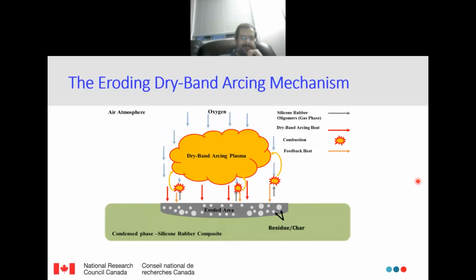Next, please. Now, this is another illustration to show how the environment, the surface, and the pollutant can all have a synergistic effect to damage the surface of the material. Here we have the silicone rubber material, and when you have dry bands, you start to have dry band arcing. So you have arcing in the presence of oxygen on the surface of the material. We have a plasma, because the arcing has a very high temperature, which can reach hundreds of degrees centigrade. This will cause some erosion, some char on the surface of the material. The main challenge now is how to develop a material that will resist the erosion and resist the damage of the surface under these very high stresses. Next, please.